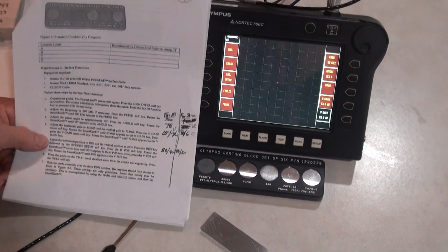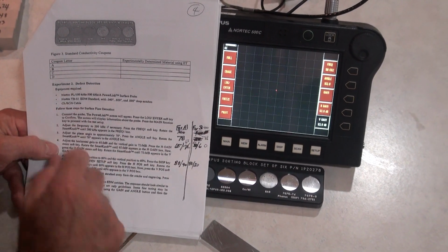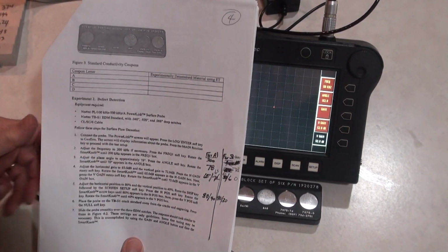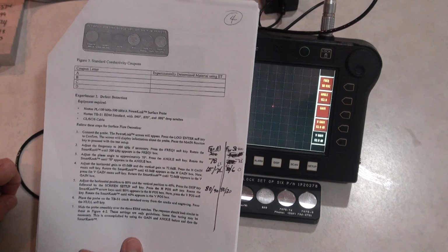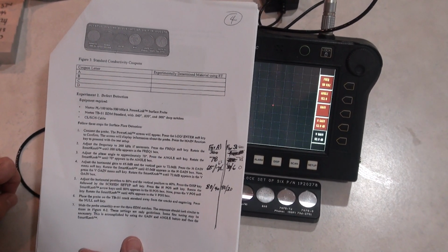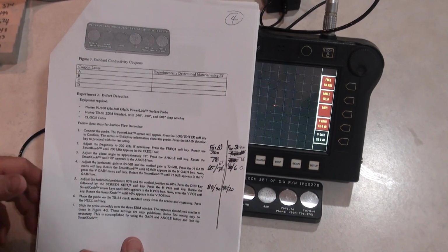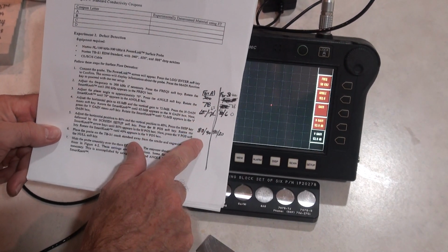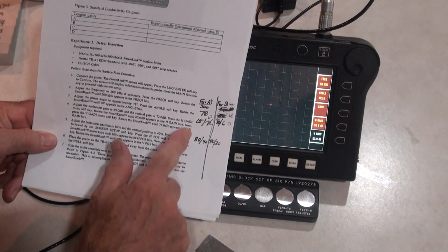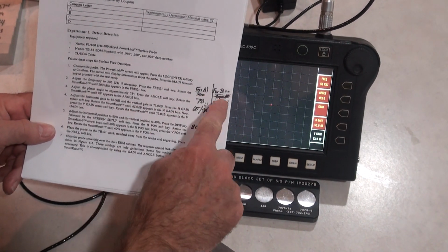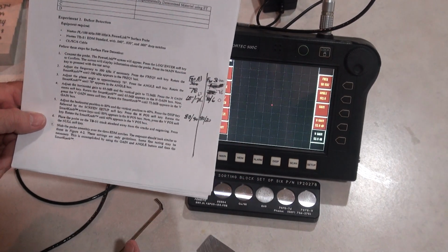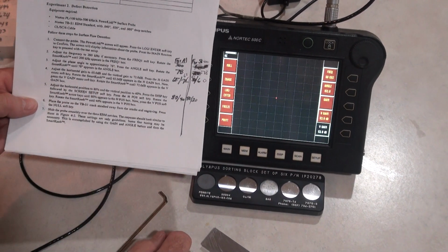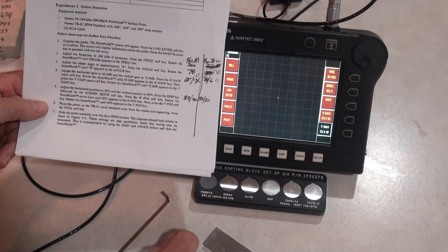Okay, so now I'm going to go to the experiment, which is called Experiment 2, Defect Detection. And we're going to have to set up our eddy current instrument a little bit differently. So I've written the procedure values for aluminum and for steel in these two columns.